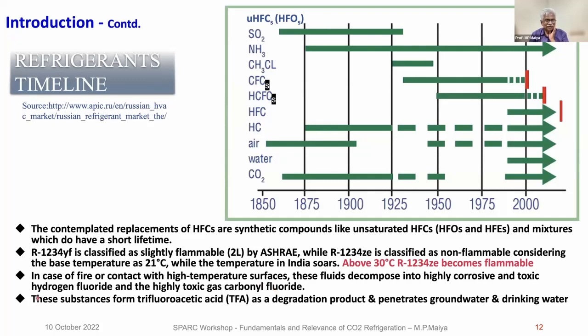And this is another one, long range. HFOs break down and make trifluoroacetic acid, TFA, as a degradation product. When it degrades, it will absorb the water and it will never come out. We can't do anything. It's done. Now it is there, it can't be removed. So this is a big problem. How to avoid it, we don't know, but people still go ahead with the HFOs. The maximum allowable concentration of 1234yf in the workplace is only 200 ppm, very little.